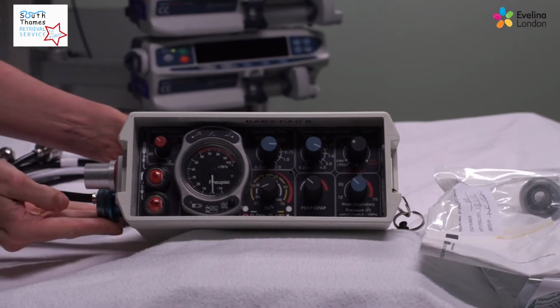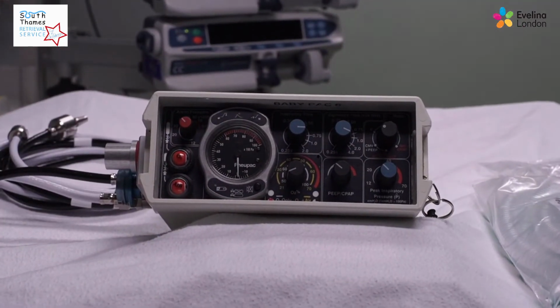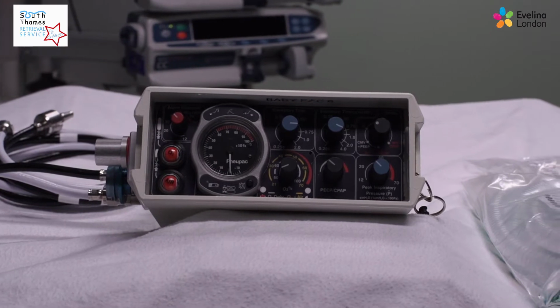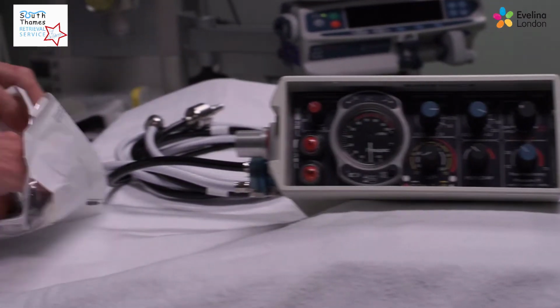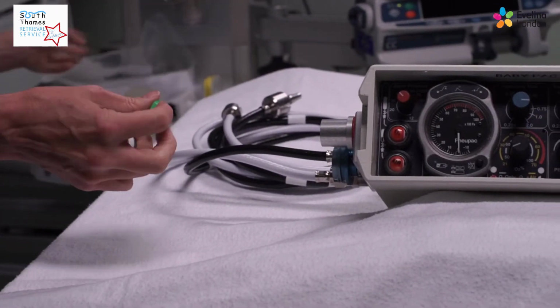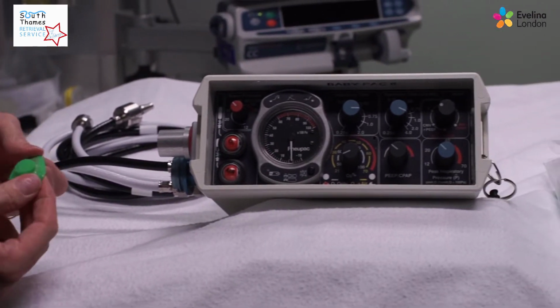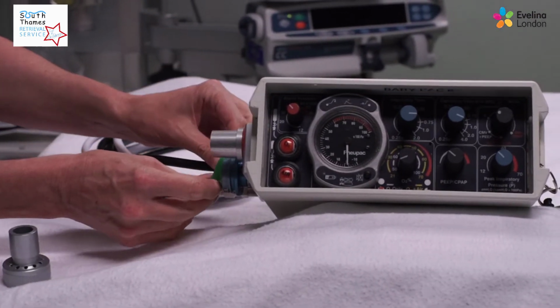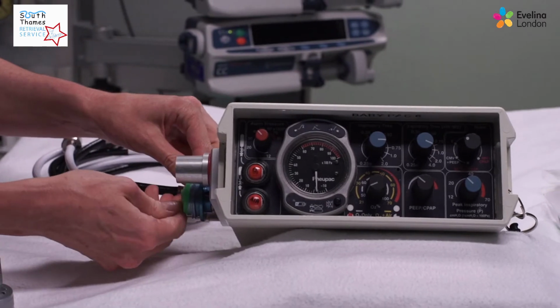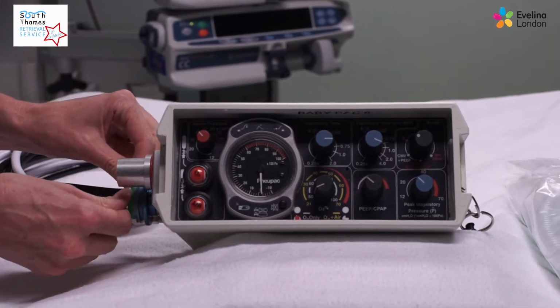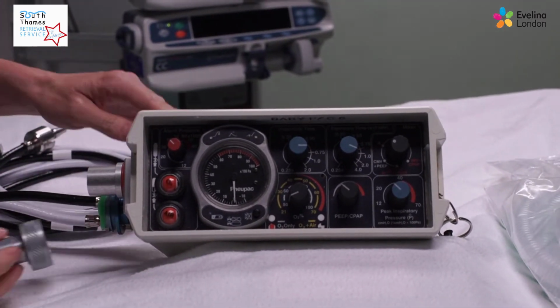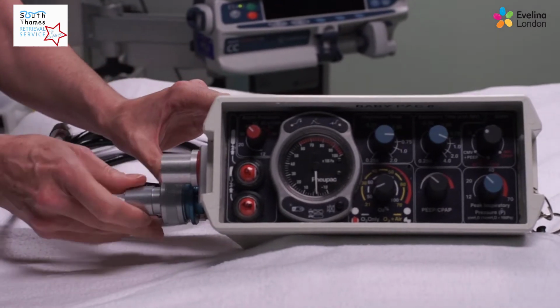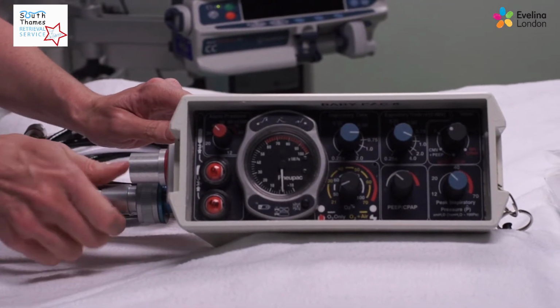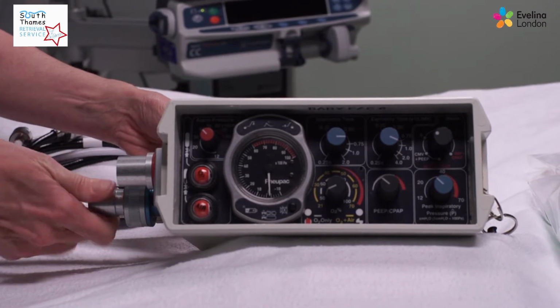We can see that the diaphragm and the hub haven't been attached, so we take one and prepare to install it. Check that the hub has no holes and slip it gently over the top, making sure the diaphragm isn't kinked. Then tighten the hub over the top, again making sure the diaphragm isn't caught in the threads.